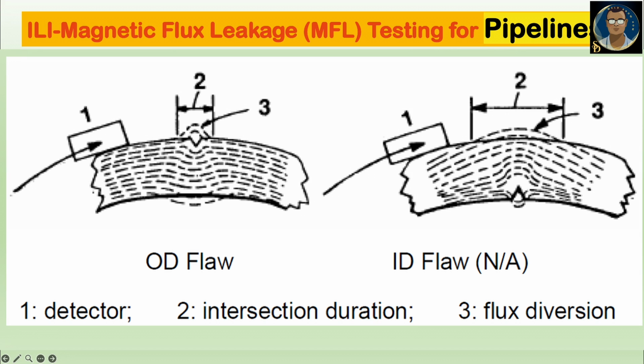As we told, it needs operator skills and experience, not only training. He should have some practical experience before he independently interprets a result. So the detector coil intersects the flux diversion of the OD flaw for a short duration, generating a voltage with a high frequency. It intersects the ID flaw's more gradual flux diversion for a longer period of time, generating a voltage with a lower frequency.